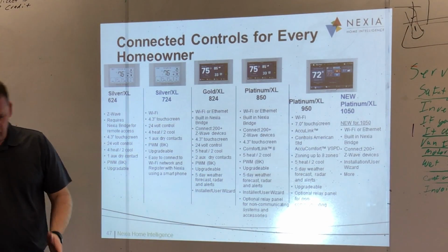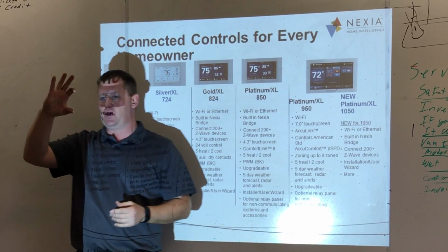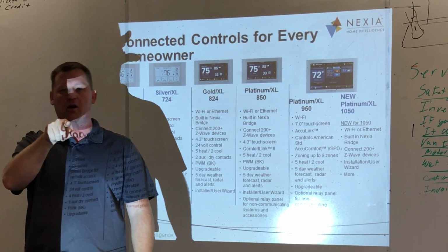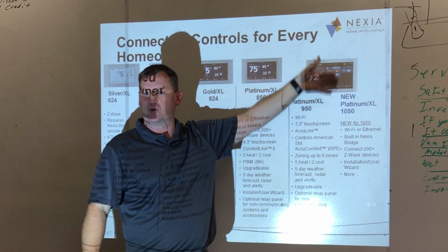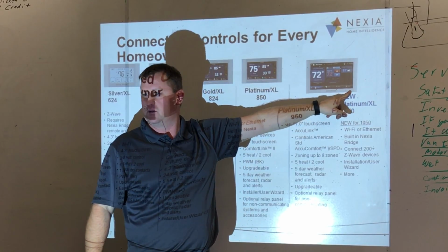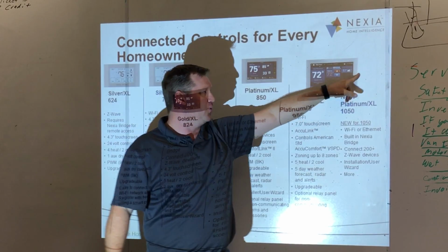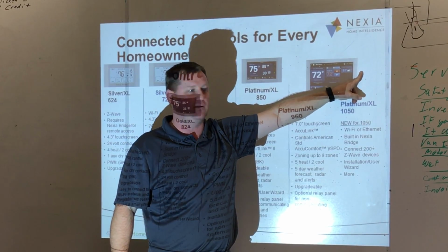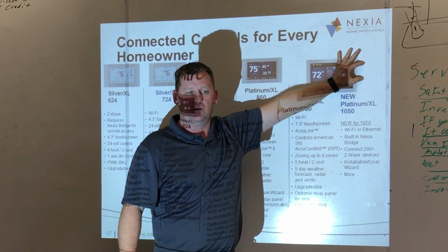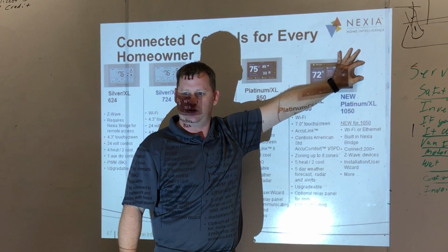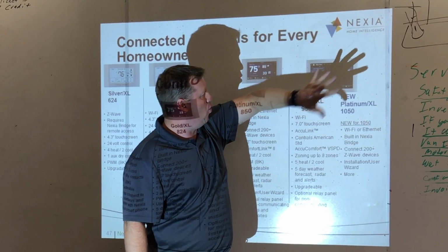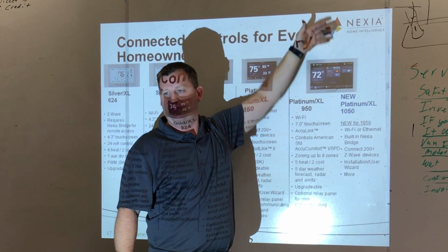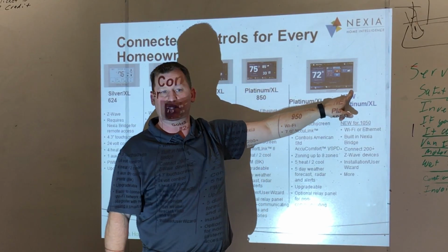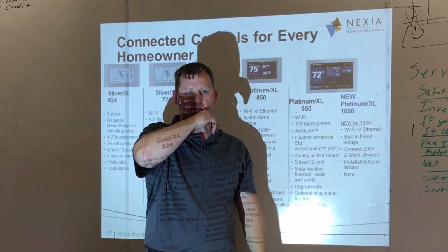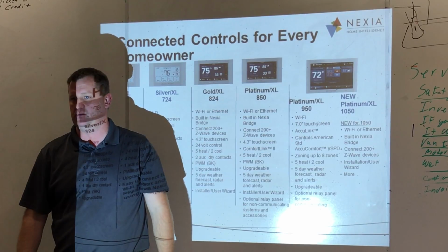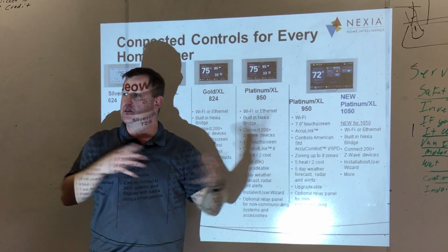One other thing: at a house with a 950 stat, a remote sensor had to be added next to it because an air pattern in the house wouldn't allow heat from the processor to come out of the stat properly, which affected the temp sensor. It irritates me that we have to do this, but when air pushes down or hits right against it, the heat can't naturally convect out, throwing the sensor reading off. It's caused as much as 13-14 degrees of error, and the house was freezing - it only happens at certain times.